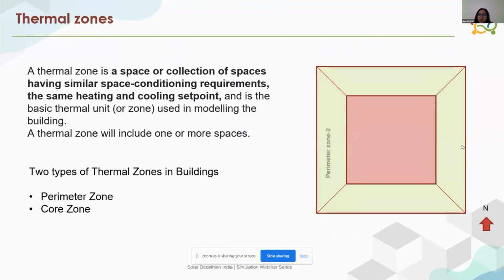There are two types of thermal zones: the perimeter zone and the core zone. As you can see in this figure, for a square plate, we have a perimeter zone on all four sides. The depth of the perimeter zone is generally 12 to 15 feet. We have four zones because solar irradiation on all four directions will be different, so north would differ from south. The external loads would be different in all four zones, giving us four types of perimeter zones and one core zone.